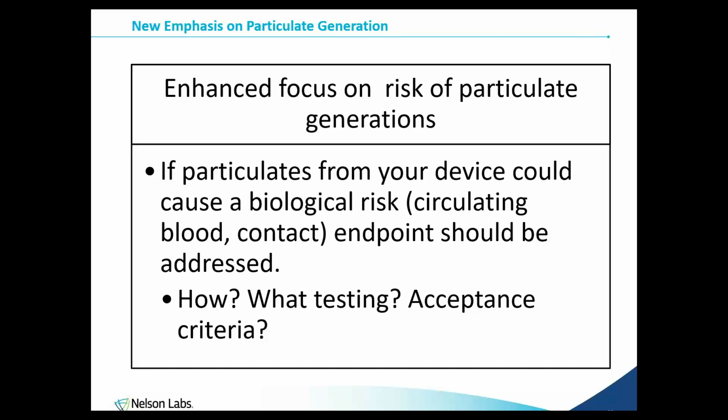In fact, I just got done talking to a company that has a bunch of vascular devices where all those vascular devices have been asked by the FDA to look at particulates because they're worried about shedding of particulates into the body. Now, from a biocompatibility process, and Preston's going to talk about this in a second, we have some good test protocols set up to look at cardiovascular devices and measure the particulates coming out. What we don't really have great for medical devices is acceptance criteria.